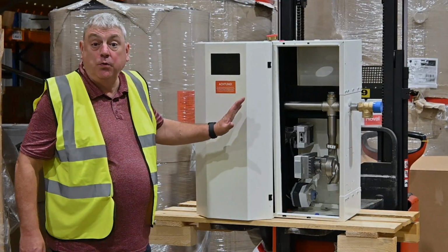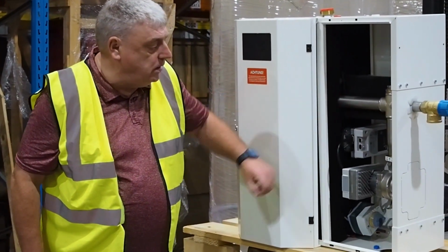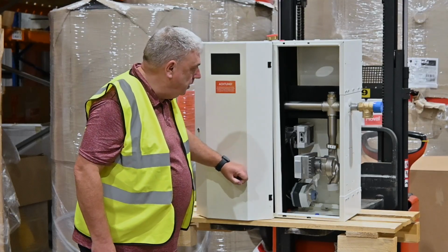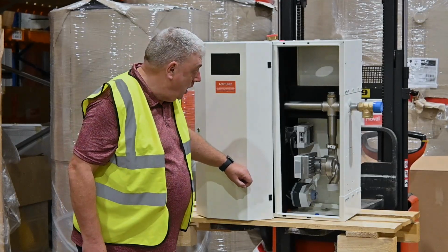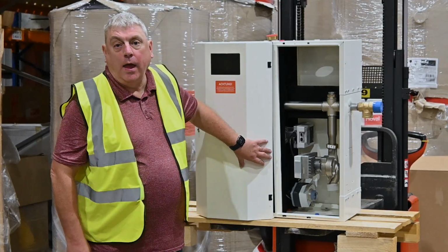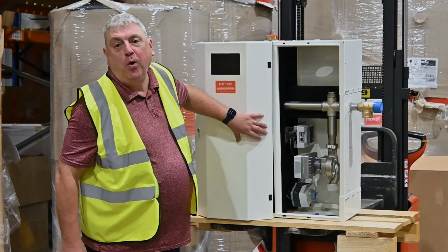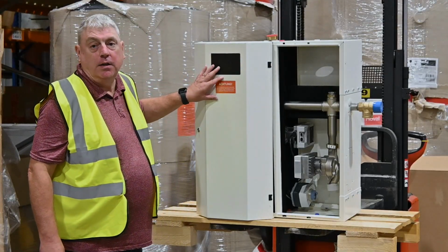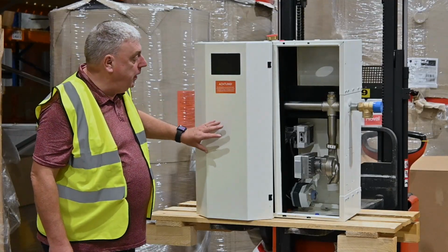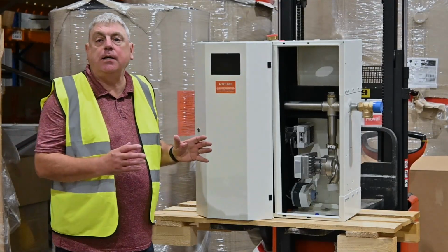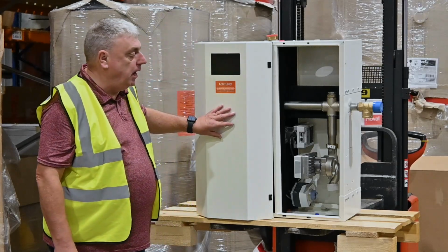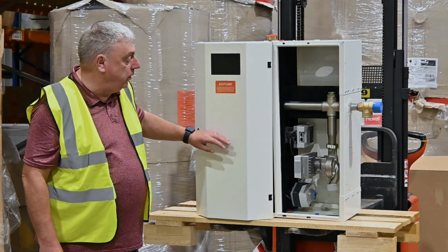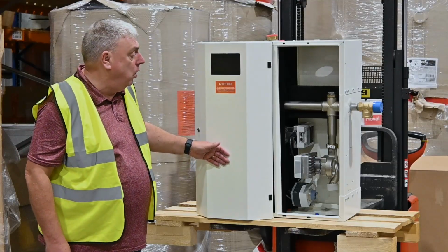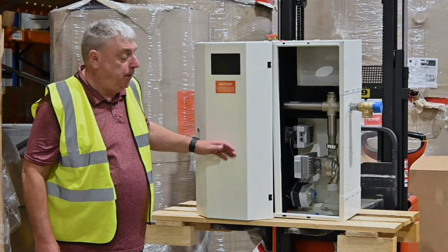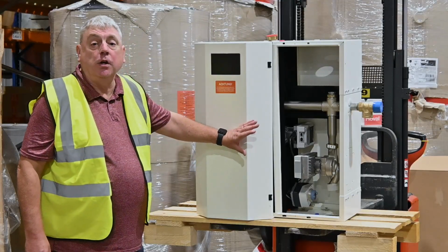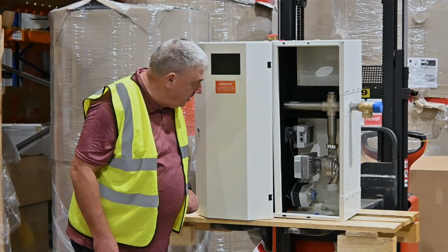Okay, having removed some of the casing and taken some of the internal insulation away, you can see that it's a relatively straightforward piece of equipment. In real life, when we're not in the warehouse, this would be hanging on a wall. And because it's a charging device, this is the TransTherm Aqua L, it would be adjacent to a stainless steel vessel. And we'd use this device to charge the vessel with secondary hot water, sanitary hot water, up to 60 or 65 degrees C.